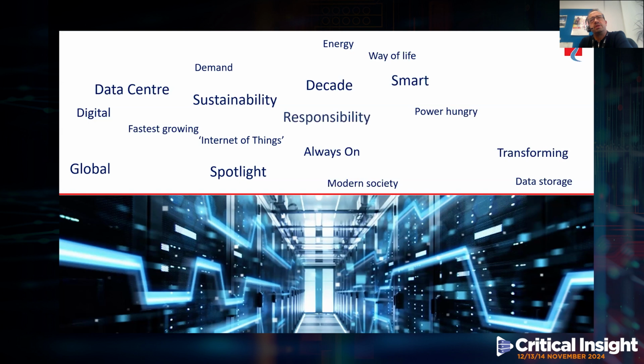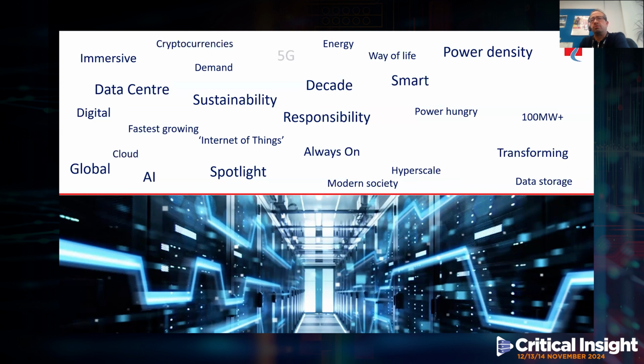Now, as a result of these demands, the data center industry is under the spotlight, having become very power hungry, meaning that sustainability is not a choice, it's our responsibility. If we just consider the last decade, server rack power density has increased fivefold. We now have high power immersive cooling systems, as we've just been seeing, and data centers have grown from 5 megawatts up to hyperscale levels, where it's not uncommon to have facilities of more than 100 megawatts.